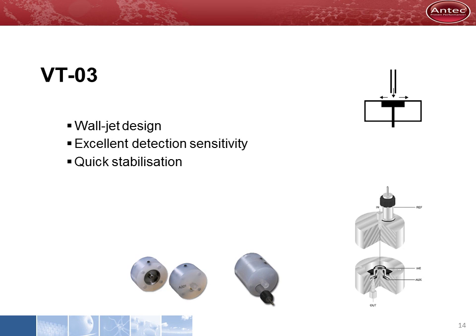The VT-03 is a wall jet cell. It has excellent detection sensitivity and a short stabilization time. It uses a polymer spacer and has an effective cell volume down to 5 nL. It is therefore compatible with standard, micro and capillary LC.